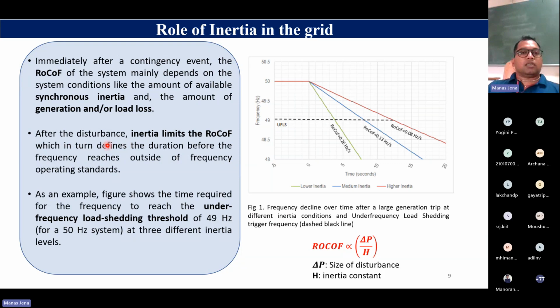After the disturbance, the inertia response that we get from the machines limits the RoCoF. As you see, more inertia, less RoCoF. So what is there in the system? There are some protection schemes which work on the principle of rate of change of frequency and low frequency. It is called low frequency demand reduction scheme, because traditionally if your frequency is going down, that means you have more load in the system than the generation, correct? So that means you have to knock out some loads. It's the last resort you want to do, but it is there, you have to do it.